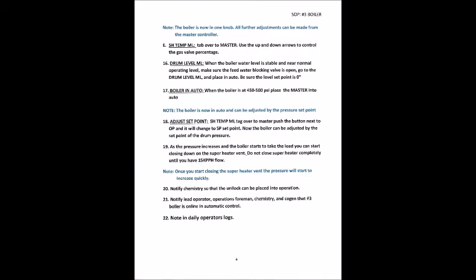16. Drum level ML. When the boiler water level is stable and near normal operating level, make sure the feed water blocking valve is open, go to the drum level ML, and place in auto. Be sure the level set point is 0. Note, the boiler is now in auto and can be adjusted by the pressure set point. 18. Adjust set point. SH temp ML, tab over to master, push the button next to OP and it will change to SP, set point.